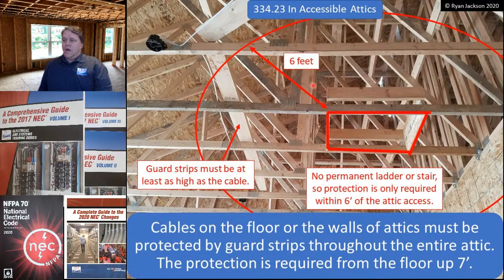Now, in my area, it's quite rare to see a permanently installed stair or ladder. So in my area, you have an attic access like this, or scuttle hole, depending on what part of the country you're in. If you have access to the attic that is not permanent, not stairs, not a permanently installed pull-down ladder, then you still have to protect everything from the floor going up 7 feet, but only within 6 feet of the attic access. In other words, I get up into the attic. For the first 6 feet, I need to be walking on wood, not wires. So guard strips, something to protect it.